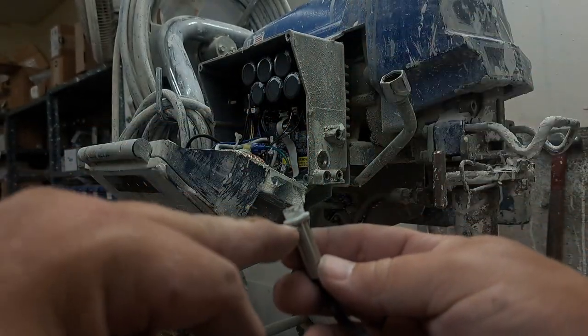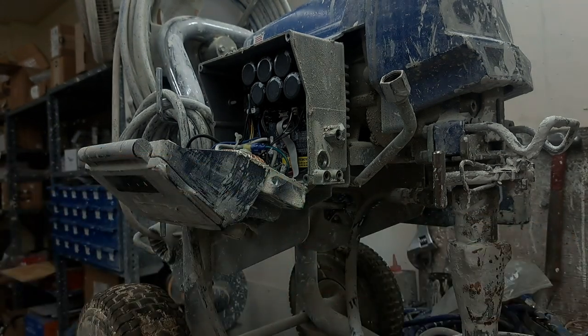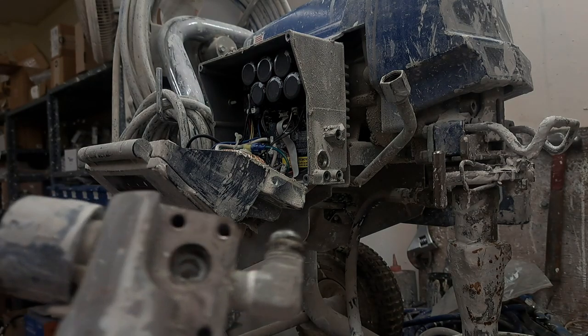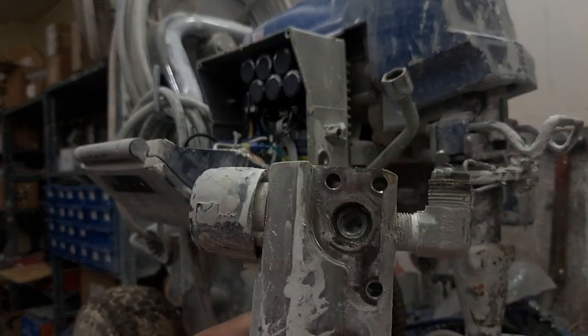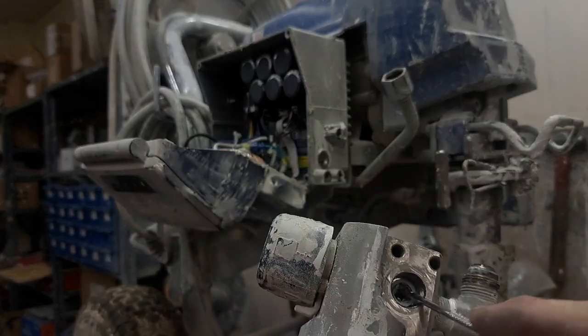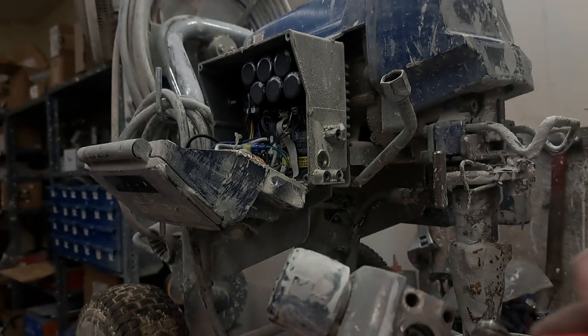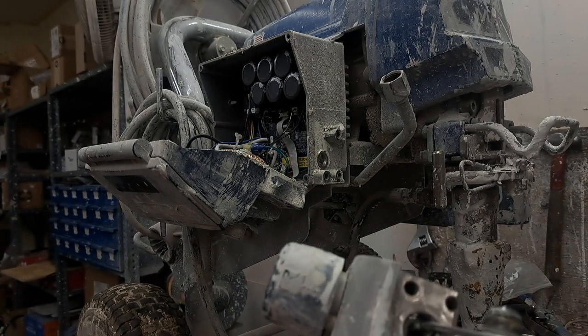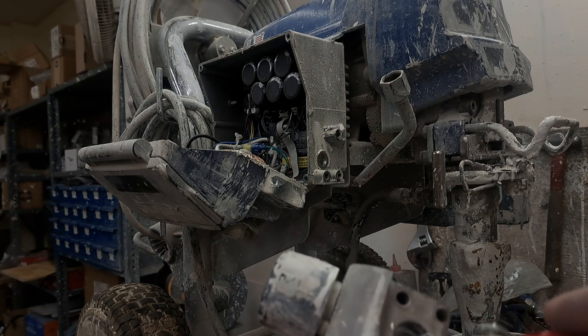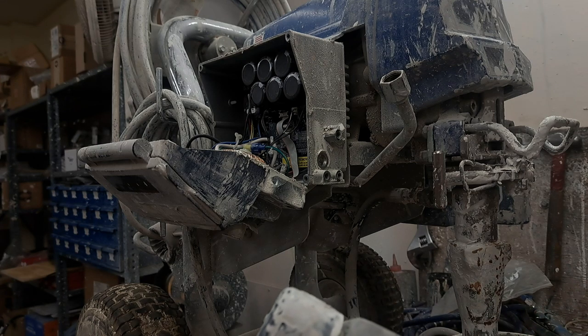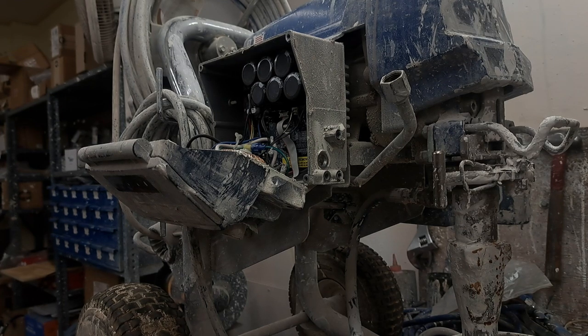On the inside, you're going to see there's a white O-ring, and there's a white O-ring right here as well. You want to make sure that one comes out. That one's not going to stay. That one you want to make sure is out. While you've got it out, look in the hole, and you'll see debris in there. Clean that debris out. It's not packed hard, so that's a good thing. If it's packed hard, that can give the transducer a false reading of low pressure. That's not the case we have here. Low pressure will make the machine want to continue to run. That's obviously not what we had going on.